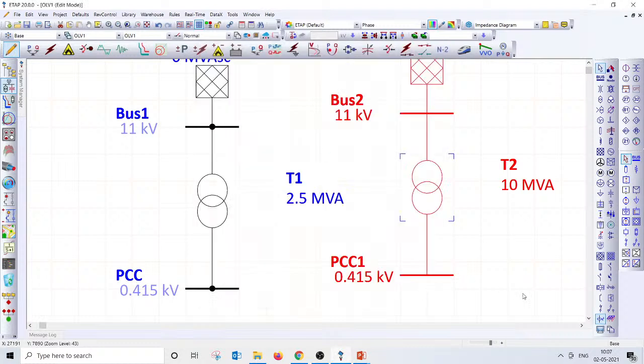I guess the numbers are visible. If not, you can go to the maximum screen and watch that, right? So the current is 524.9. I guess you're able to see those numbers, right? And the full load current on the LV side is 13,912 amps. What is wrong with that? If I go with the low voltage circuit breaker, unfortunately, we do not have circuit breakers of more than 6,300 amps.